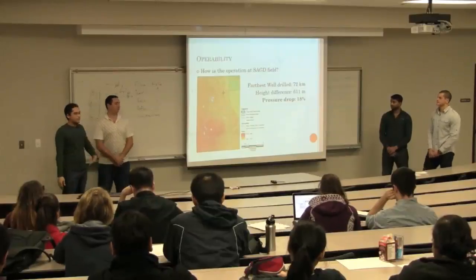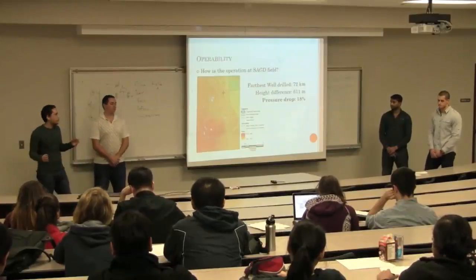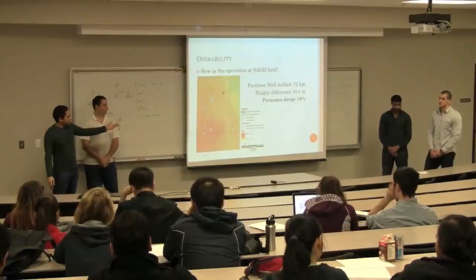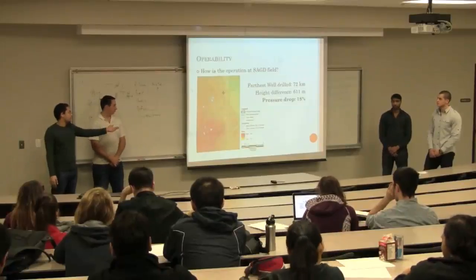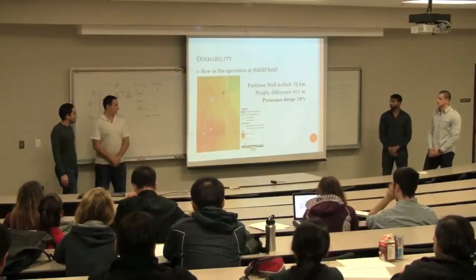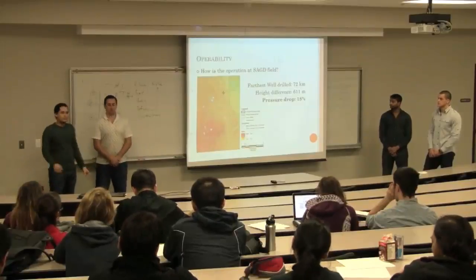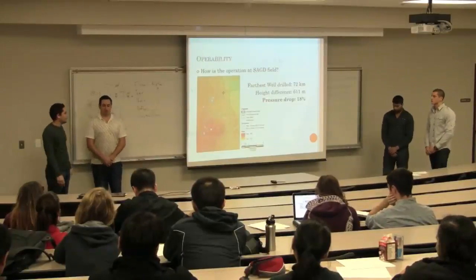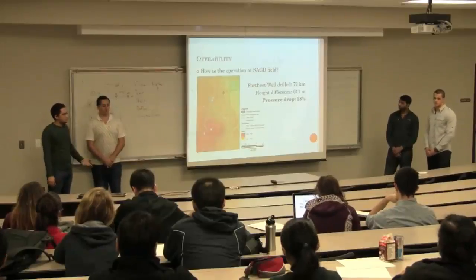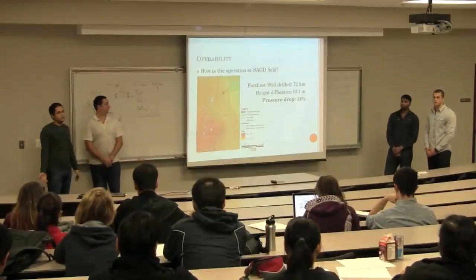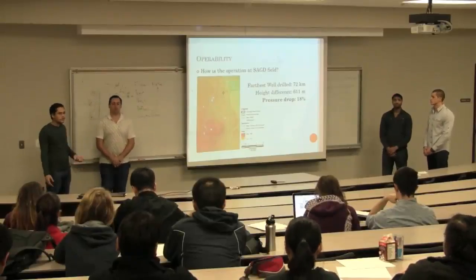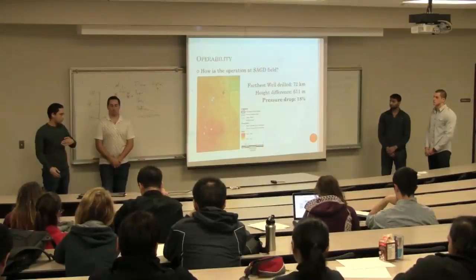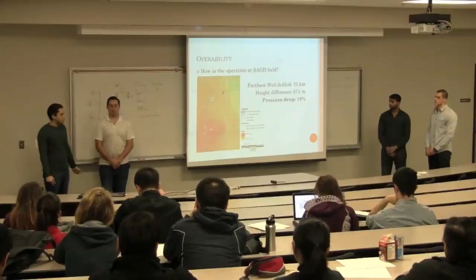And we got a worst case scenario for the steam transportation. So the steam is produced at the facility and needs to be injected at the farthest well drill, considering the height difference from the facility. And we calculated the pressure drop for this transportation to be about 18% of the pressure produced at the steam generation unit. An alternative to prevent this pressure drop would be to increase the capacity of the unit by 20% or install pumps along the pipeline to prevent this pressure drop.